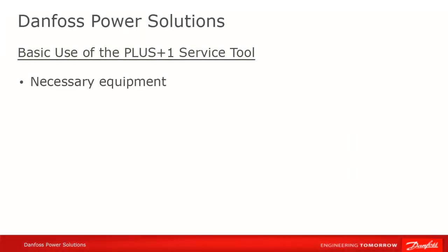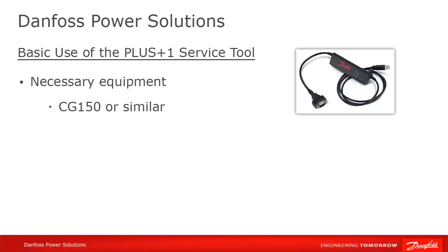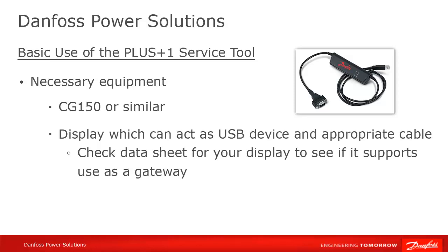In order to use the service tool, you'll first need an appropriate gateway. This can be either a Danfoss CG150 or a Danfoss display, which can act as a USB device with an appropriate cable. You can also use another manufacturer's gateway, as long as it follows the RP1210B API.